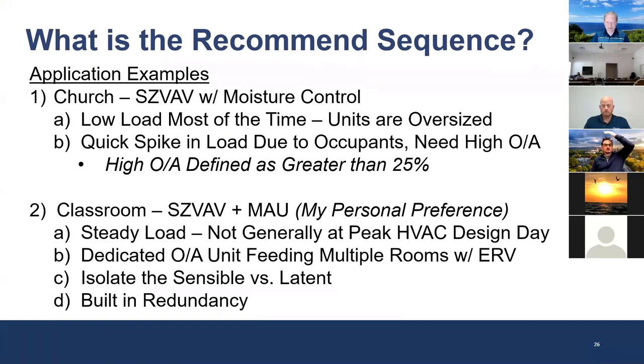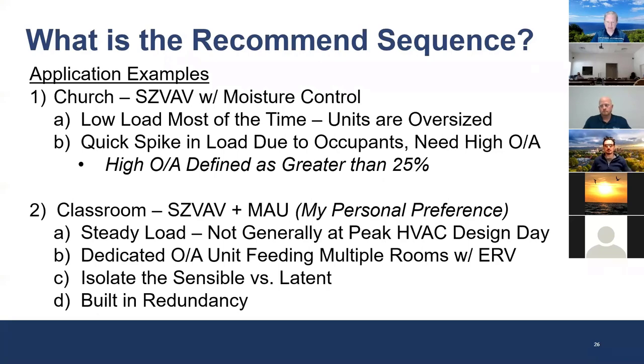We actually had a customer who kept seeing a humidity spike — they were sterilizing a procedure room between every procedure, mopping floors and cleaning every surface with a five-gallon bucket of sterilizer. You can design for that, but most of the time you design knowing there will be a spike and you manage how long it takes to recover. If any moisture loads are high, you're probably looking at a latent design piece of equipment. The best way to go through these is with applications and examples. Let's start with a church: best served by a single zone VAV with moisture control. It's low load most of the time, so units are extremely oversized.